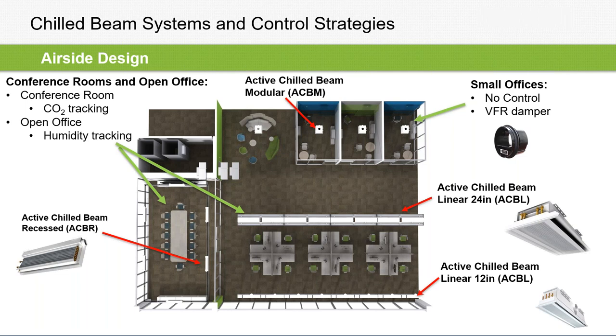So what I normally would recommend is really two things. One would be an after-hours humidity set point in the space, where after the humidity level gets to a certain point at night, your equipment turns on, kind of like a night setback for temperature. And then the other would be very similar to what we would call an optimum start-stop for temperature, but this would be an optimum start-stop for humidity.